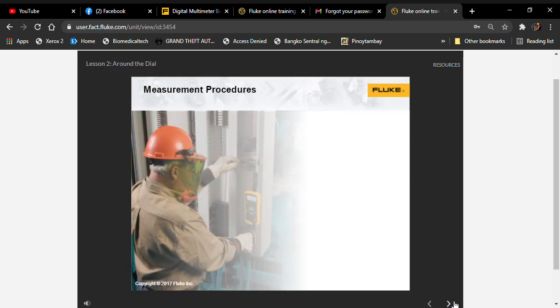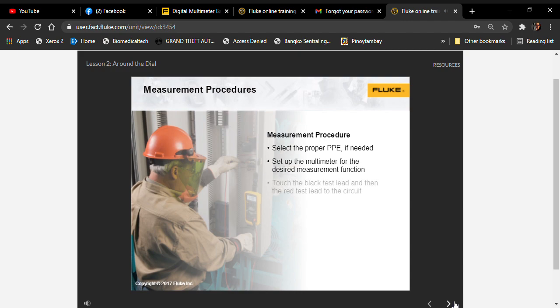The procedure for making a measurement is similar for all functions. First, you must wear the proper PPE for the task. Then, set up the multimeter for the desired measurement function. This involves selecting the desired function using the rotary function selector switch, then plugging the test leads into the correct input jacks. Next, connect or touch the test leads to the appropriate point on the equipment or circuit under test.